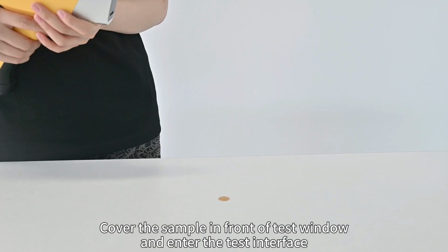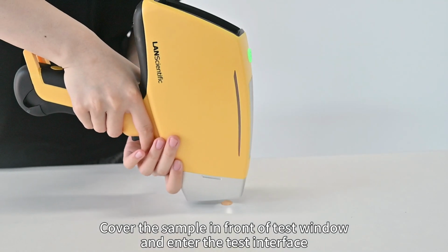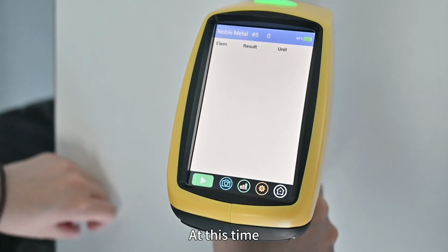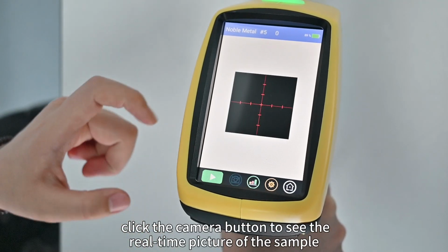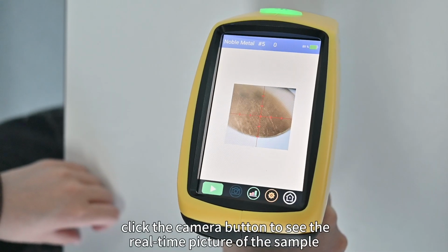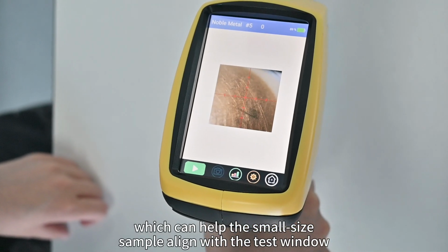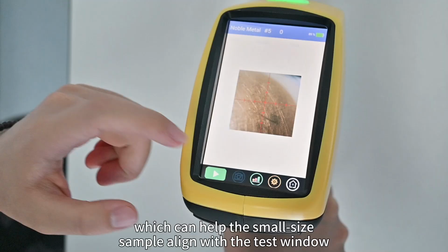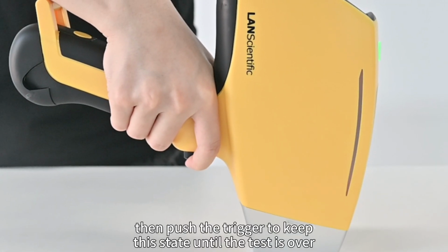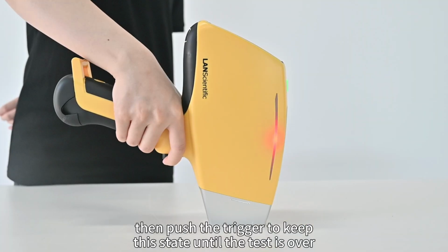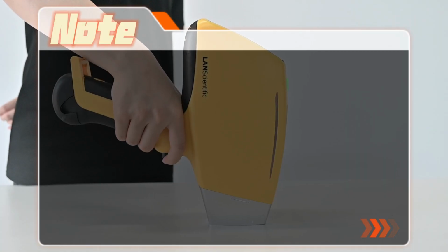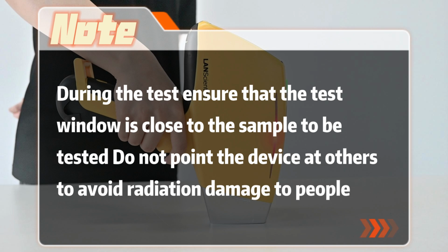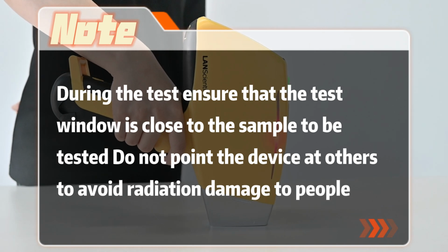Step 3. Testing sample. Cover the sample in front of the test window and enter the test interface. At this time, click the camera button to see the real-time pictures of the sample, which can help the small size sample align with the test window. Then push the trigger and keep that state until the test is over. Note: during the test, ensure that the test window is close to the sample to be tested. Do not point the device at others to avoid radiation damage to people.